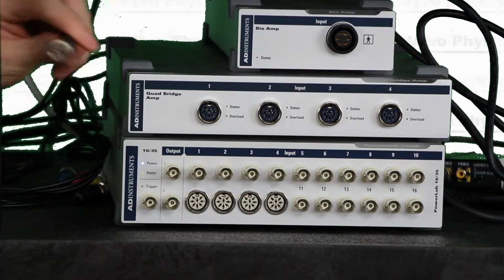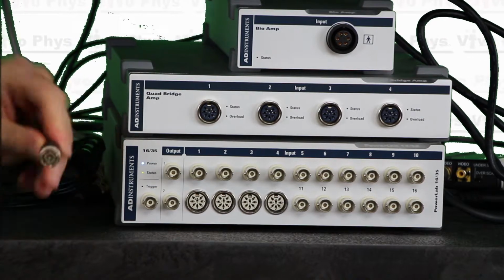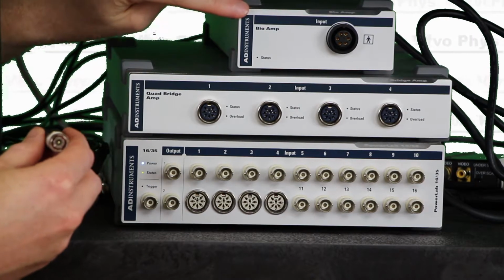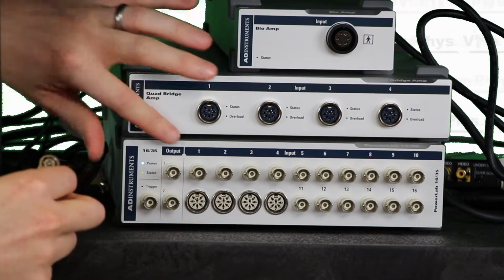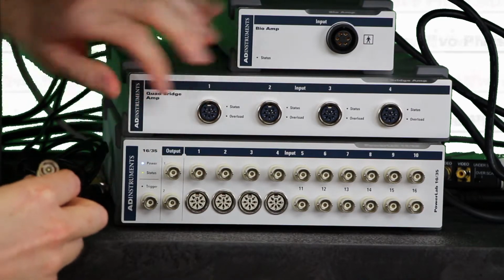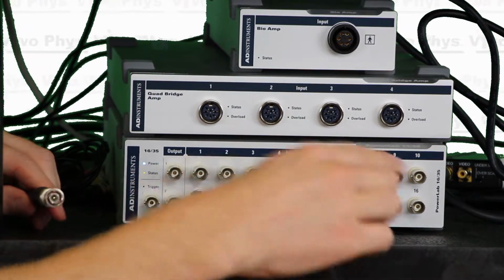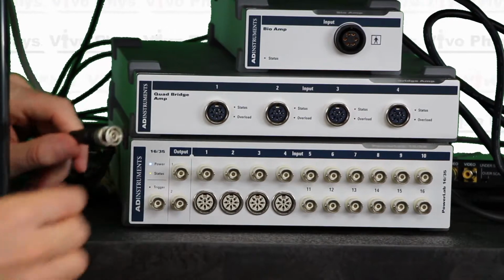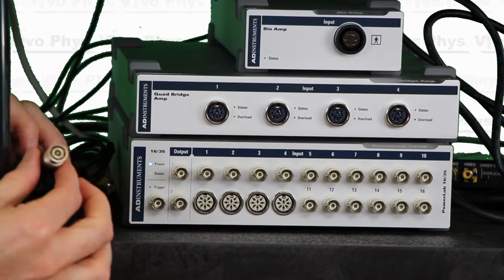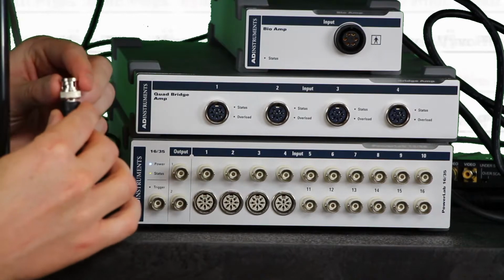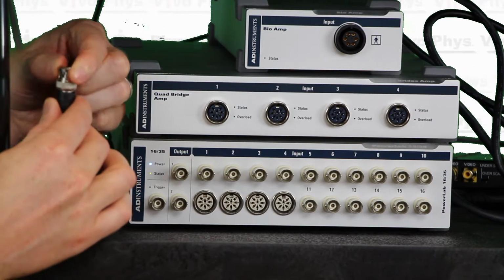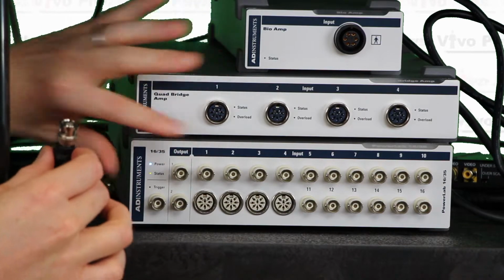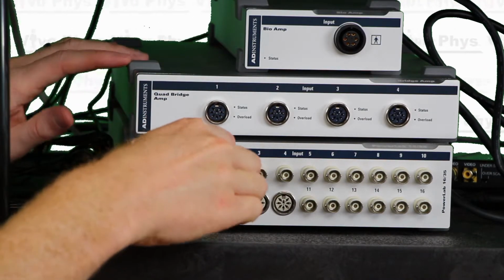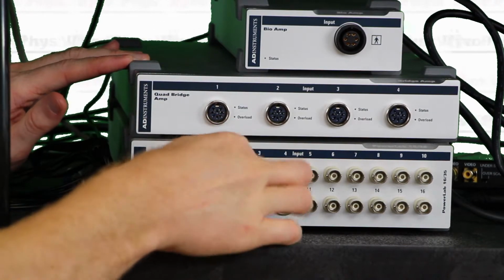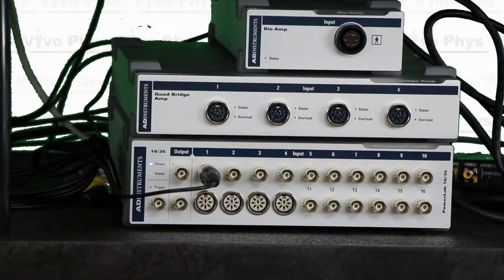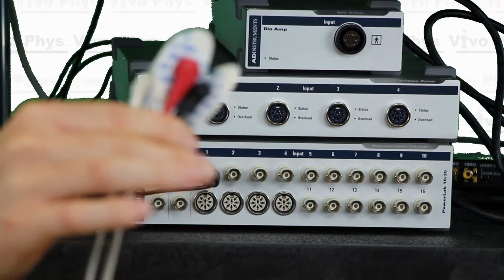So here is the black BNC cord that is plugged into the back of this bioamp box. I'm going to plug it into the first channel here. So there's channels listed 1, 2, 3, 4 and so on on the front of the PowerLab. When you plug this in, you're going to push it in, and then it's got a little top here that's sort of a screw top that you're going to screw onto the channel. So I'm going to plug it in, push it in, and then give it a little screw until it locks into place.